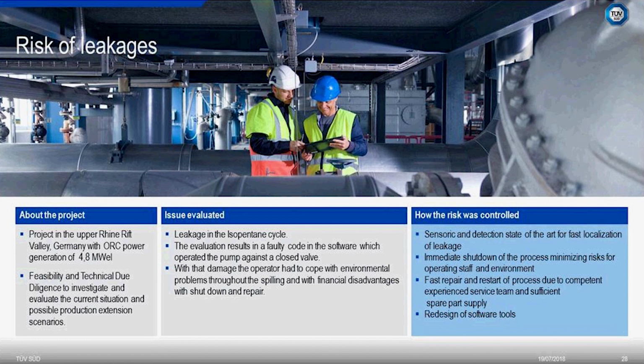against a closed valve. This produced a higher pressure inside the piping system and caused leakages at the valve and also at the piping, which brought a lot of damage to the operator. On one hand they had to cope with the environmental problems of emitting isopentane into the environment, and the safety issues for employees. And of course this also caused a financial disadvantage for the operator, with the shutdown of the power plant and all the repair costs to cope with.